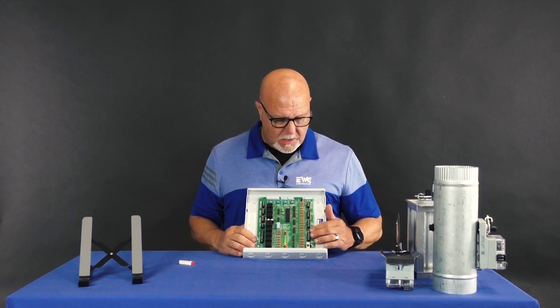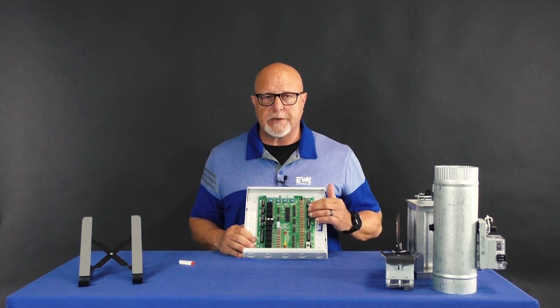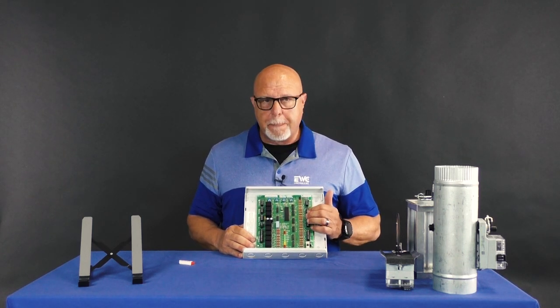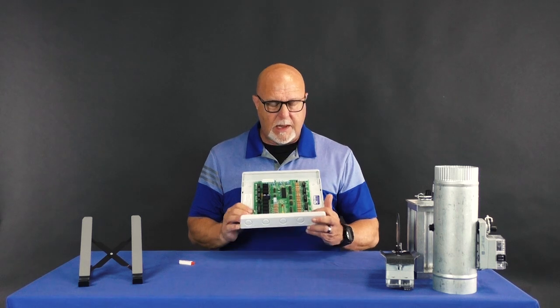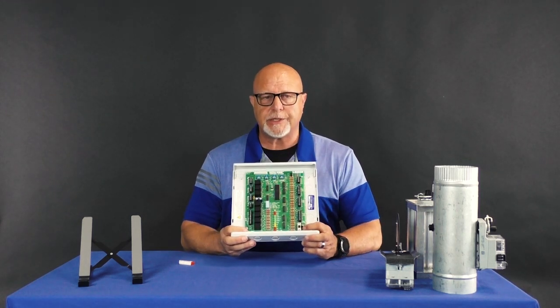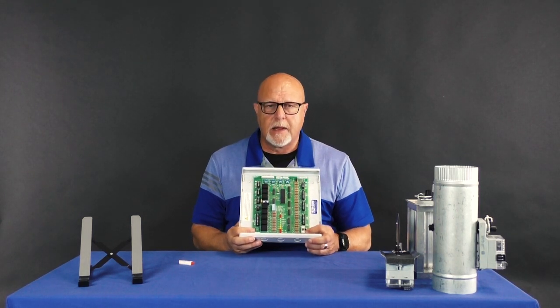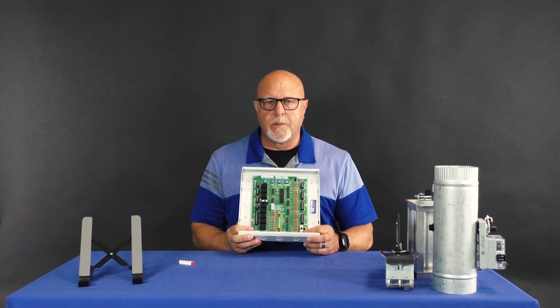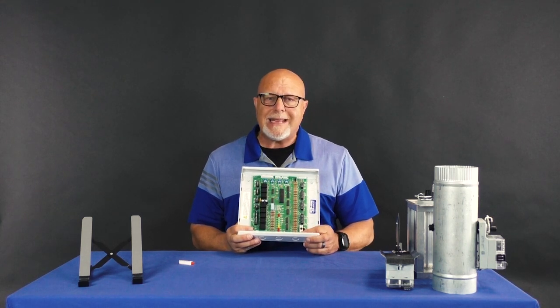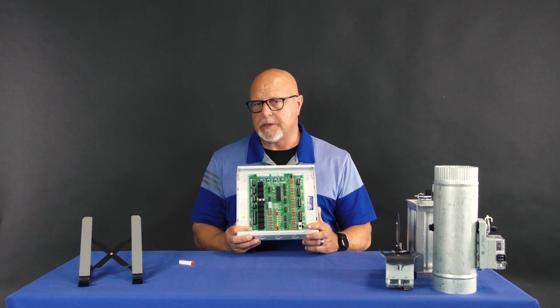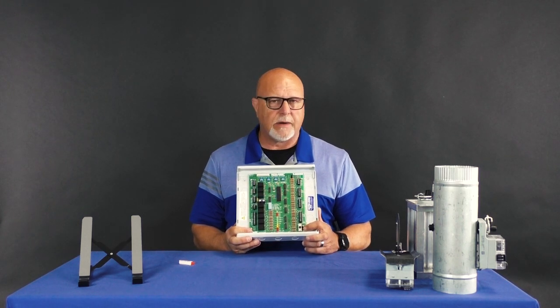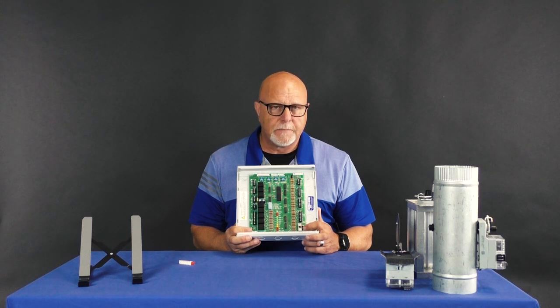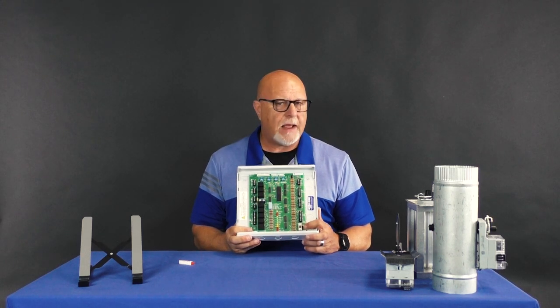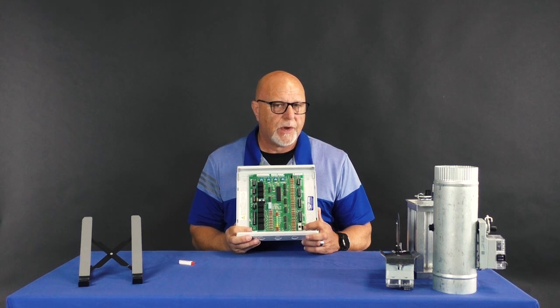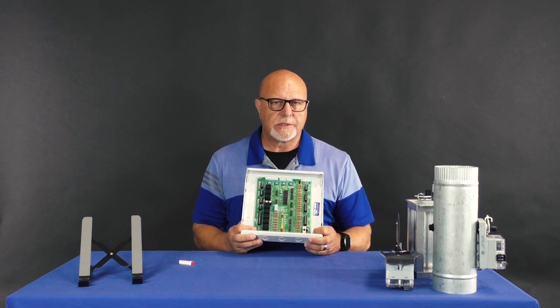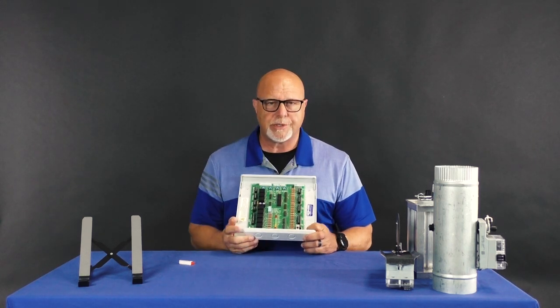Your thermostats are all wired in over here on your thermostat terminal block side. And you also have an emergency heat selection switch. If you remember, in the beginning I mentioned that with EWC you can use both heat/cool and heat pump stats on this board. And if you were to put a heat/cool stat on a heat pump system, the heat/cool stat doesn't have an emergency heat selection switch that allows the homeowner to go to the thermostat and manually turn on emergency heat.